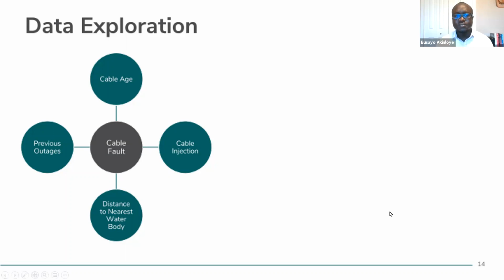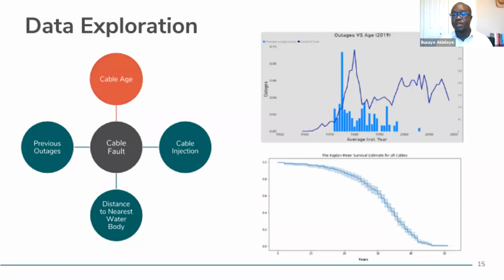Let's go to the next slide and start with cable age. Here I have 2 graphs. The top one shows the demographic distribution of our underground cables versus the actual outages in 2019. The blue line graph shows the demographic distribution based on installation year. For example, cable installation started in the 1960s, ramped up to its peak in the 1980s, then came down and became steady into the 2000s. But looking at the 2019 outages, shown as blue bars, the majority occurred on cables installed between roughly 1970 and the 1990s.